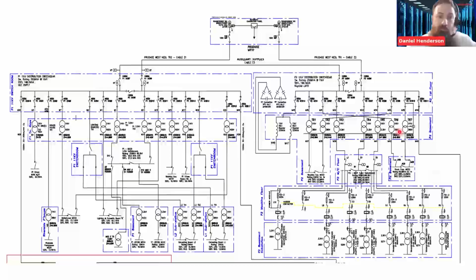And the timing on the circuit breaker that tripped, I think it ended up, was somewhere around 3 to 4 seconds. So what should have happened in that eventuality on this transformer, when that transformer did fail, your protection's going to be expected to go on this circuit breaker here. So I'd have expected this to trip. If that didn't trip from a coordination perspective, I would expect this circuit breaker to trip. If that didn't trip for whatever reason, I'd then expect this one to trip, and this one did. So it was sat at around 3 seconds, 4 seconds before that trip, which is much too long for what you'd expect your coordination to do.